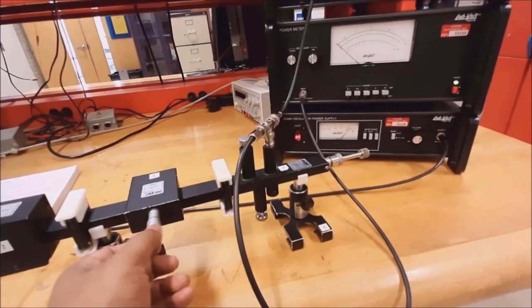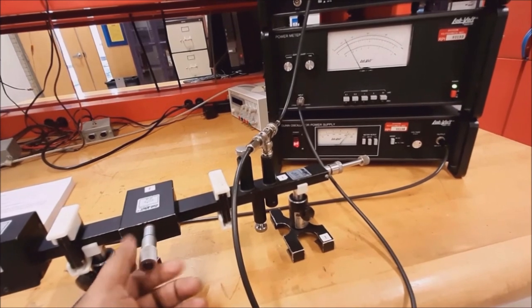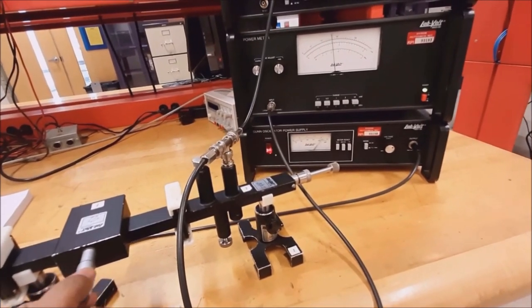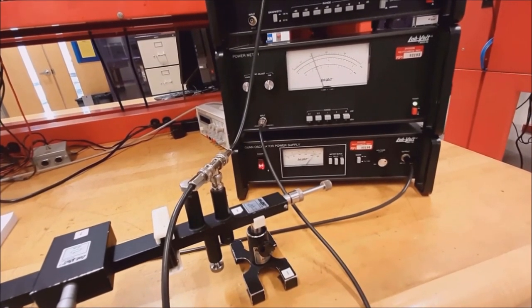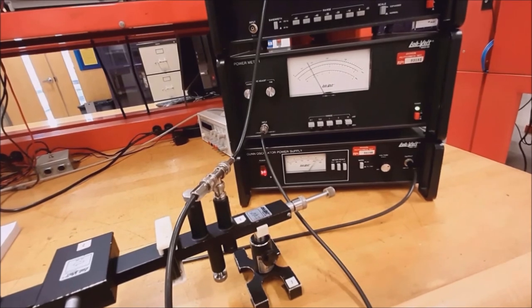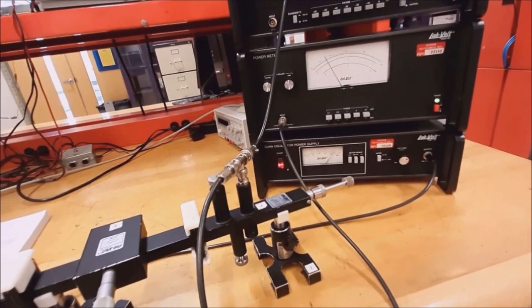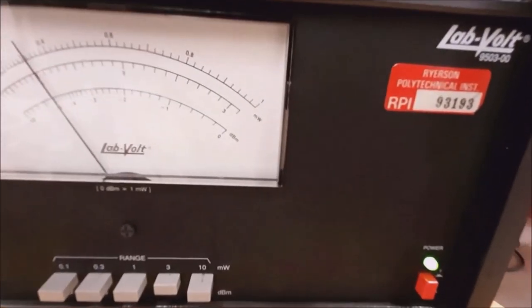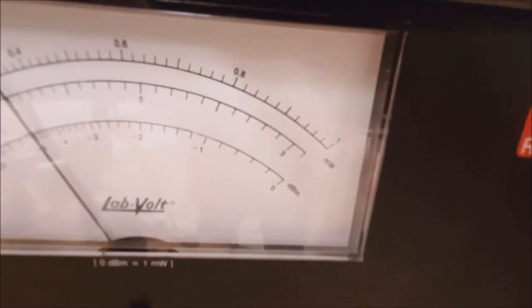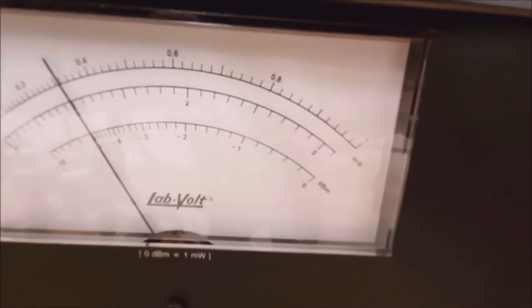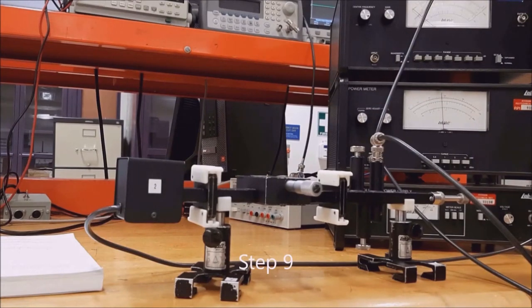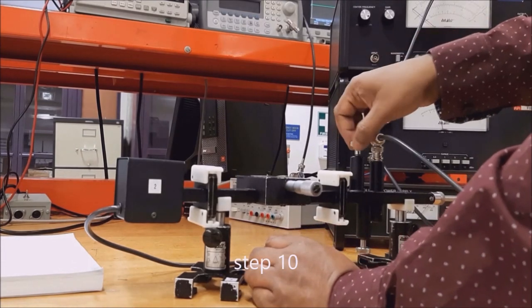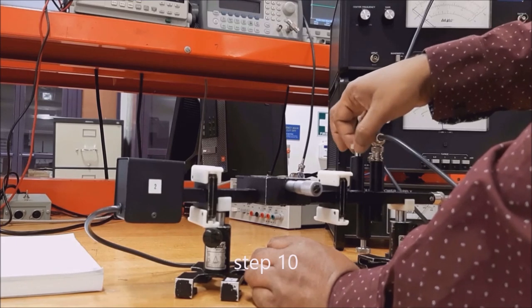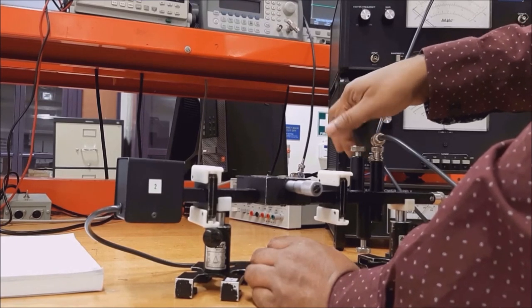Now I apply one milliwatt power from the variable attenuator. So I adjust the micrometer position to get 1 milliwatt power. You can see if I apply 1 milliwatt, the consequence will be shown on the power meter. The signal level will get down. Now I am playing with the matching screws to maximize the power level. So you see the power level is going up from 1 milliwatt.